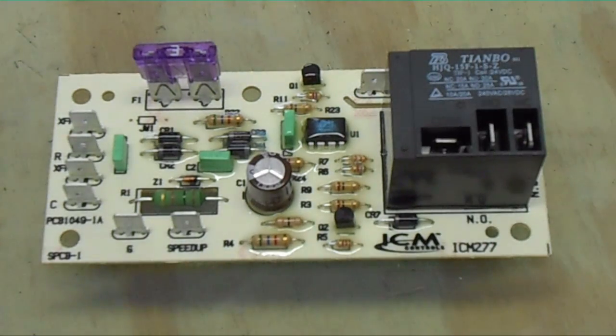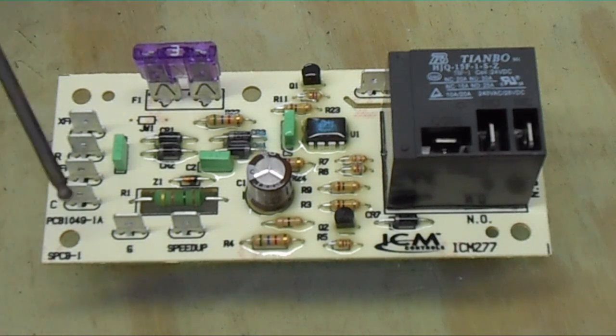We have terminals on the side. Of course we have our fuse right here — a 3-amp fuse. On the side it says XFR, and the third one down is XFC. The top is the red from the transformer — 24-volt hot — and XFC is the common from the transformer. After it leaves these two terminals, it'll leave on the R and C terminal and go to the field wiring — the field low voltage connection — taking care of all four of these wires entering R and C and exiting R and C.